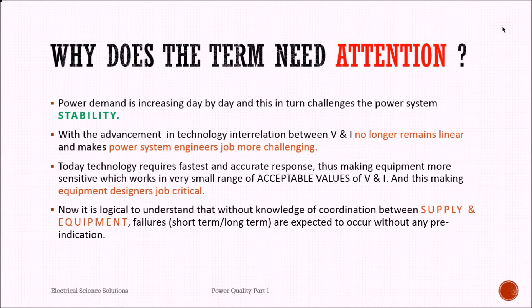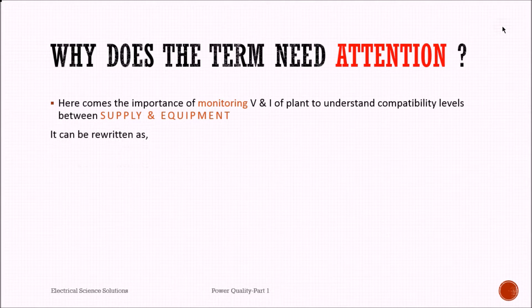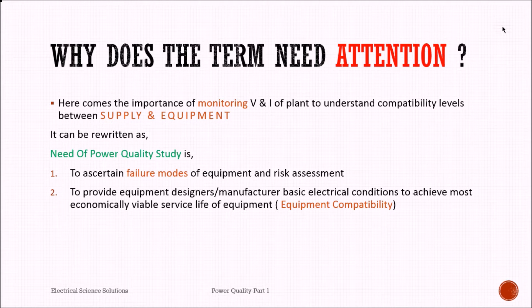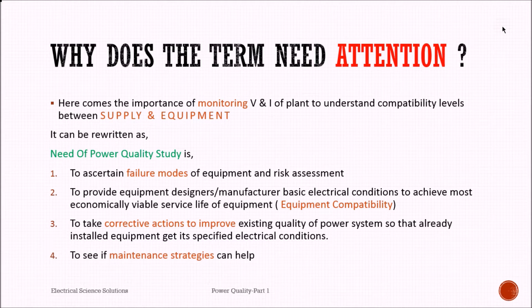Now here comes the importance of monitoring voltage and current of a plant to understand compatibility levels between supply and equipment. So it can be rewritten as: need of power quality study is to ascertain failure modes of equipment and risk assessment associated with it. To provide equipment designers a basic electrical conditions to achieve most economically viable service life of equipment. You can say this can be considered as equipment compatibility. To take corrective actions to improve existing power quality of power system so that already installed equipment gets a specified electrical conditions. Finally, to see if the maintenance strategies can help.